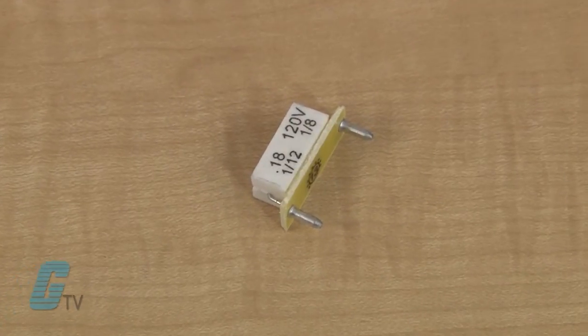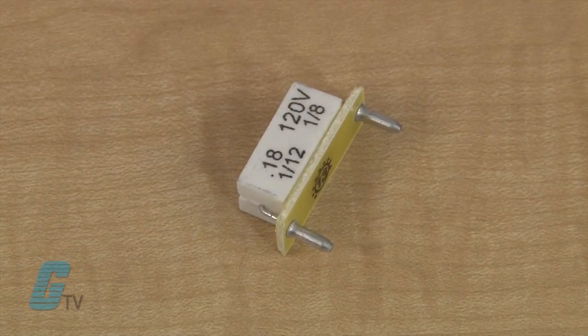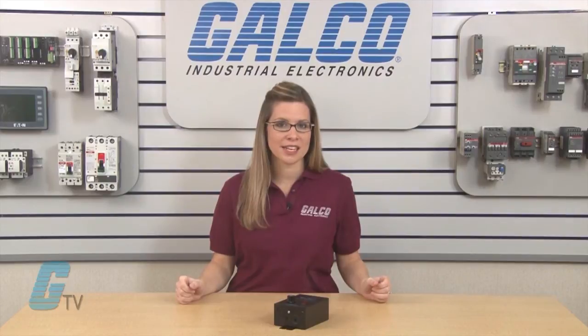The device uses plug-in horsepower resistors that automatically preset the drive's IR comp and CL circuits for safe operation on various motors. These horsepower resistors are sold separately and can be sized to fit the needs of the motor.